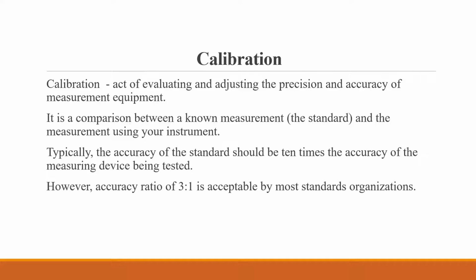According to most organizations, a 3-to-1 ratio with the standard is acceptable when you compare your accuracy. Right now, many of us use pipettes, draw pipettes, or MLA pipettes. How do we calibrate them? How often do we calibrate them? Do we even calibrate them? Do we check that if it's supposed to deliver 1.0 ml, or 0.10 ml, or 0.25 ml, that they really deliver that much?